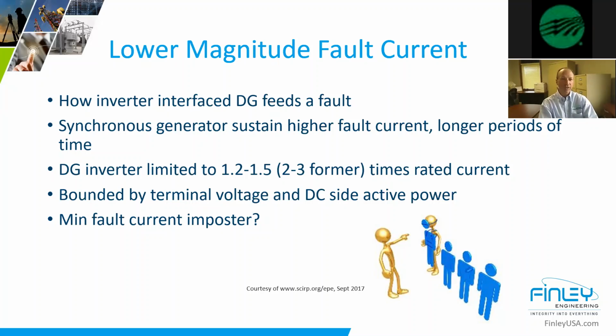But with a DG inverter, especially with power electronics, they used to be more like 2 to 3 times rated current for magnitude contribution, rather than your 7 to 10 times. The newer inverters are sometimes limited to 1.2 to 1.5. I thought that was astounding when I read some literature on the newer hardware revs of these devices. That's amazing, but that brings up another question.